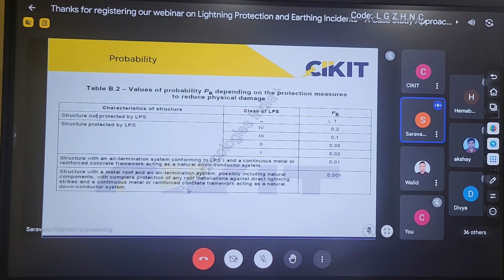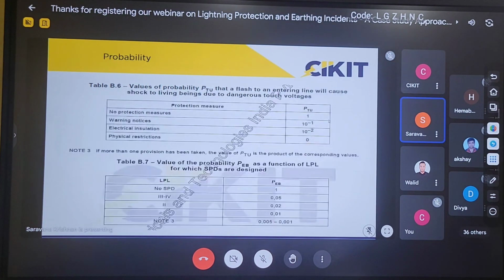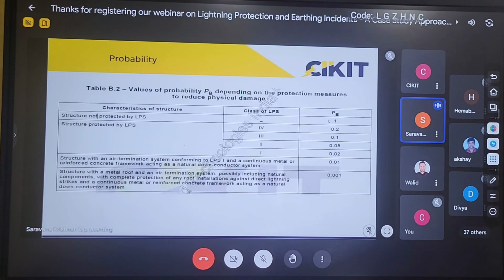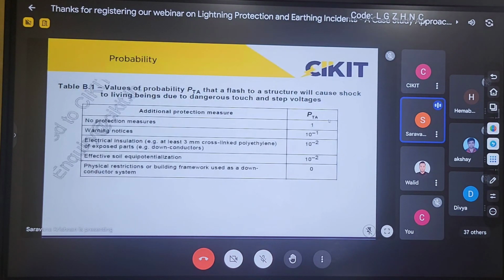So the third one, PTU, is related to the danger because of dangerous touch voltages. If lightning is striking on the power line, the touch voltage won't come into the picture, because the impulse current is traveling only through the power line. So here we will be considering only touch voltages, whereas for the first one, PTA, we will be considering both touch as well as step voltages, because there the lightning is striking on the structure.